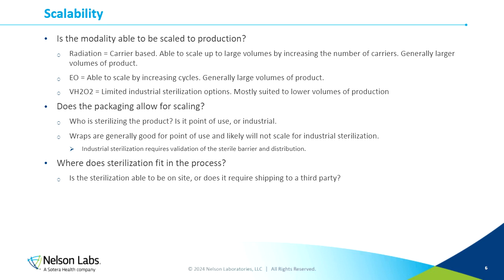So the other consideration with that is, who is going to be sterilizing the product? So is the product going to be provided terminally sterilized, or is the intent for point of use? Is it going to be industrially sterilized via a large scale processor? Essentially, who is going to be doing that sterilization is a consideration. The other is, wraps are generally good for point of use. So our packaging is a consideration when it comes to who is going to be sterilizing it. If it's going to be point of use, wraps are a good option, but wraps generally don't scale very well for industrial sterilization and providing product as sterile. Usually in those situations, instead of providing the wrap as the sterile barrier, you're adding an additional packaging layer, such as a pouch or something like that.